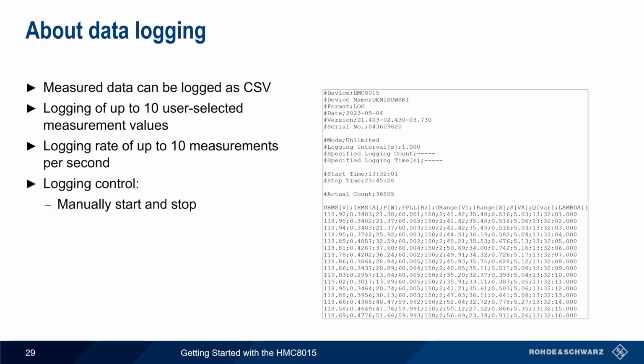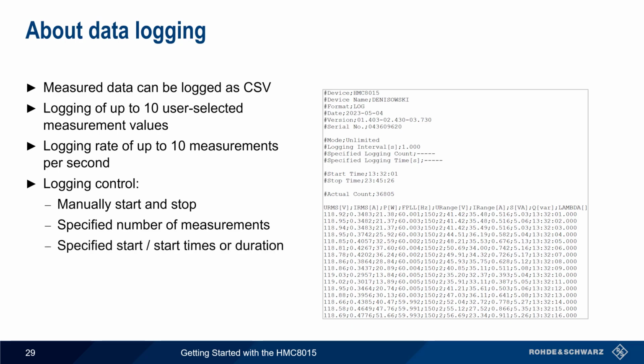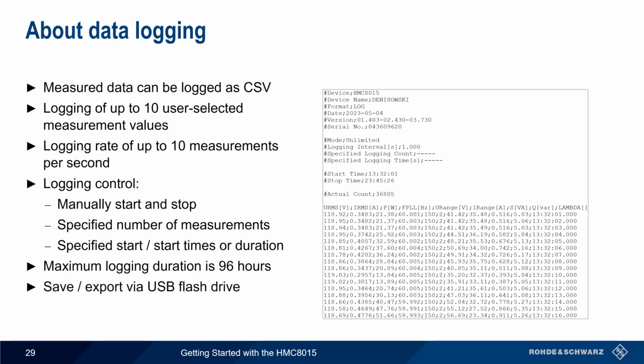It can be manually started and stopped. The user can specify a given number of measurements to make, or the absolute start and stop times or durations can be configured. The maximum logging duration is 96 hours, and the log CSV data can be easily saved to or exported via an attached USB drive.